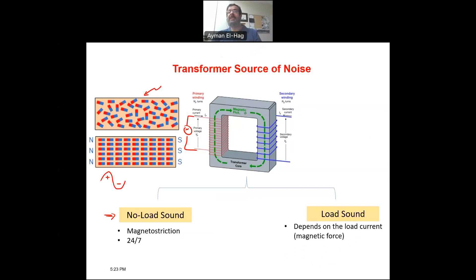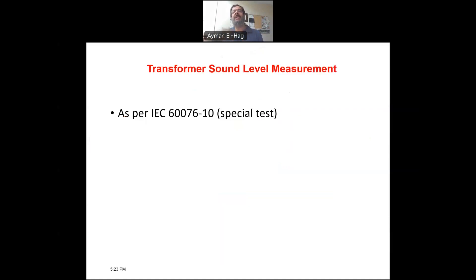So this is why some users of the transformers want to make sure that the level of the transformer is not that high, especially if they install the transformer close to residential loads. So for this we might ask the manufacturer to do some testing and try to tell them what is the level of noise coming from those transformers. Is it acceptable level or not? And for this we follow the IEC 60076-10 and measurement of the transformer sound level is considered as a special test.